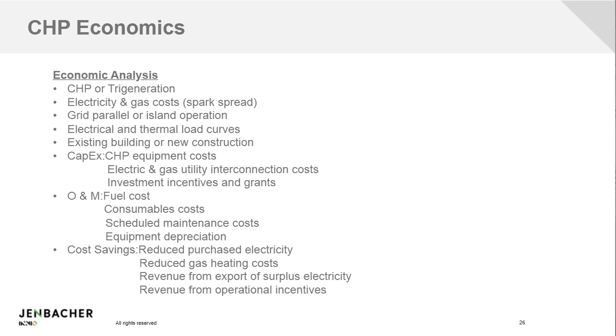Is the system you're looking at going to be operated grid parallel or in an island type operation? Grid parallel means it runs parallel to the grid all the time, using the grid as a reference and combining those two streams of electricity to feed downstream loads. Island operation would be isolated from the grid and operate independently. It's not necessarily that the grid isn't there, it's just not connected to it.